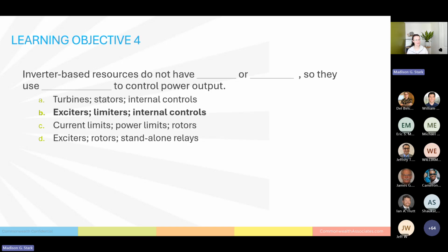And then as far as the standalone relays versus internal controls, standalone relays don't control power output. They trip power output. They shut off power output. So that's a big difference between the internal controls versus standalone relays in the system. Your internal controls are what's going to determine how much and what kind of power is coming out of this relay or is coming out of the inverter, whereas a standalone relay is more so looking for operating conditions that now exceed what we're looking for, and we're going to trip. So those are a little bit of a nuance between the internal controls versus standalone relays, and some of the nuances between turbines specifically as far as exciters, limiters, etc.